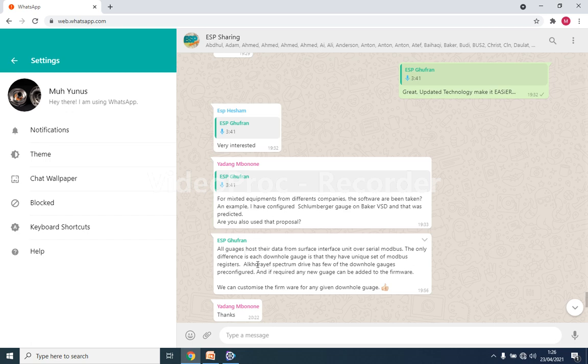This answer is from Brother Gufran: all gauges hold their data from the surface interface unit over serial Modbus. The only difference is that gauges hold unique sets of Modbus registers. Al Khorayef Spectrum drive has a few of the gauges pre-configured, and if required, any new gauge can be added to the firmware on the surface.